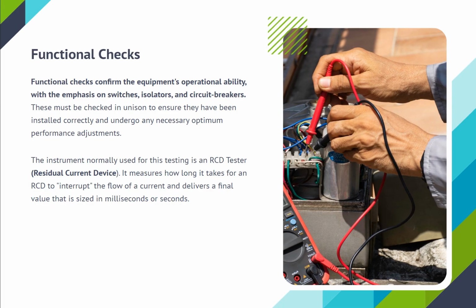Functional checks. Functional checks confirm the equipment's operational ability, with the emphasis on switches, isolators, and circuit breakers. These must be checked in unison to ensure they have been installed correctly and undergo any necessary optimum performance adjustments.